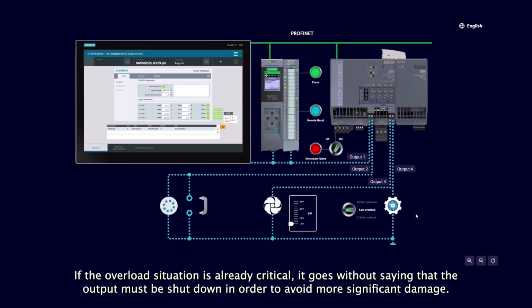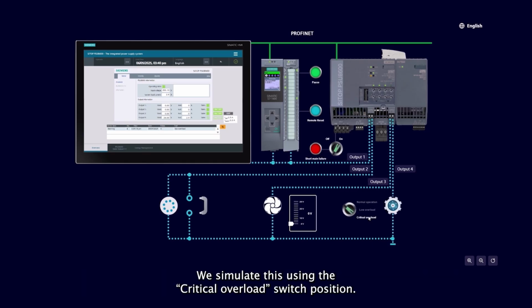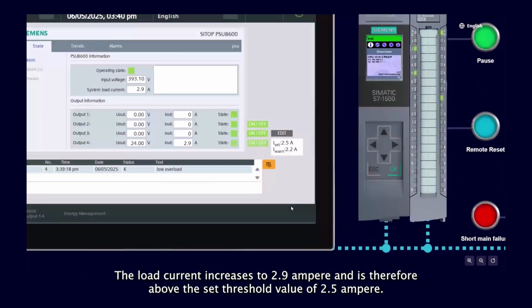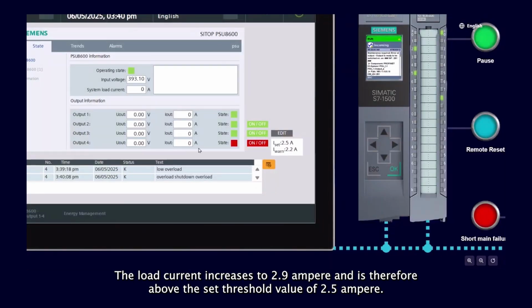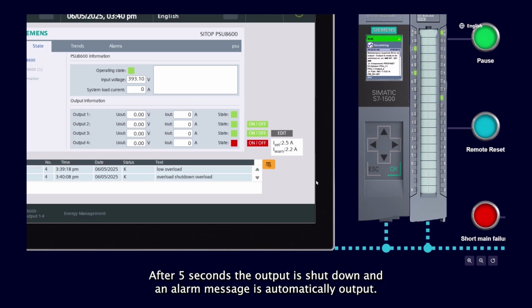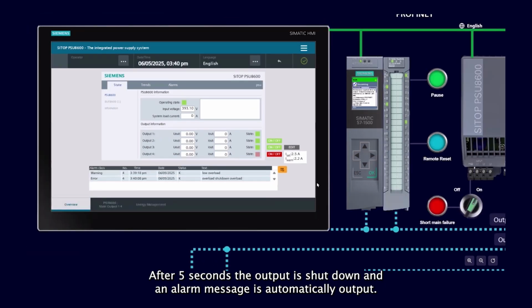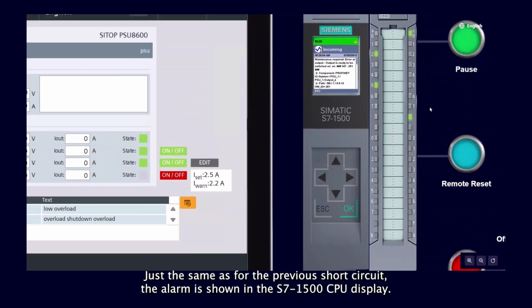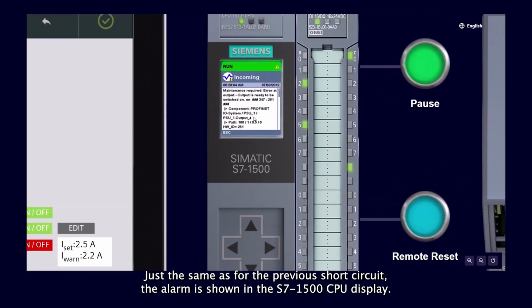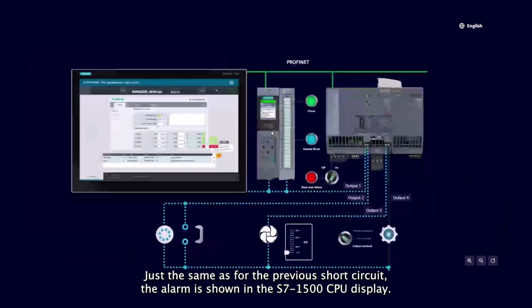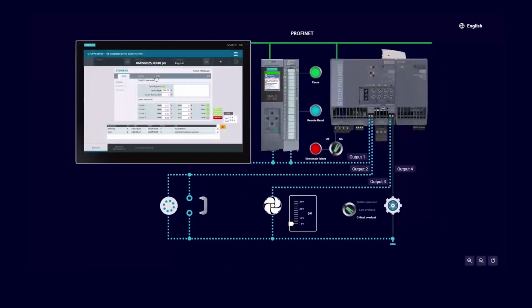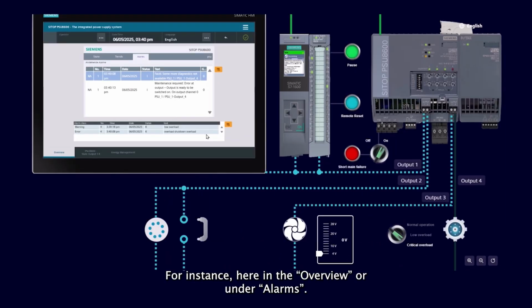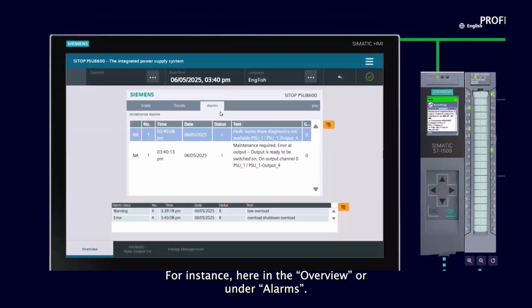If the overload situation is already critical, it goes without saying that the output must be shut down in order to avoid more significant damage. We simulate this using the critical overload switch position. The load current increases to 2.9 ampere and is therefore above the set threshold value of 2.5 ampere. After 5 seconds, the output is shut down and an alarm message is automatically output. Just the same as for the previous short circuit, the alarm is shown in the S7-1500 CPU display and in various faceplates, for instance, here in the overview or under alarms.